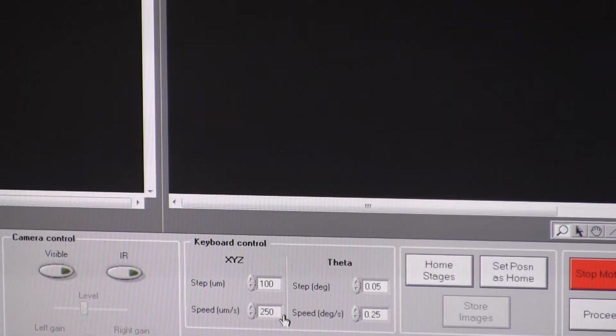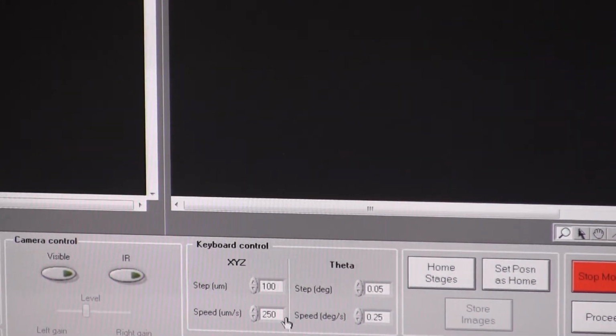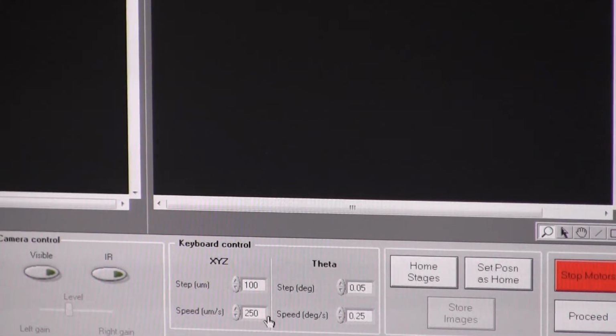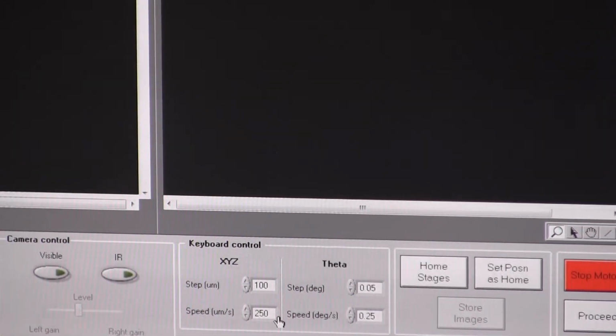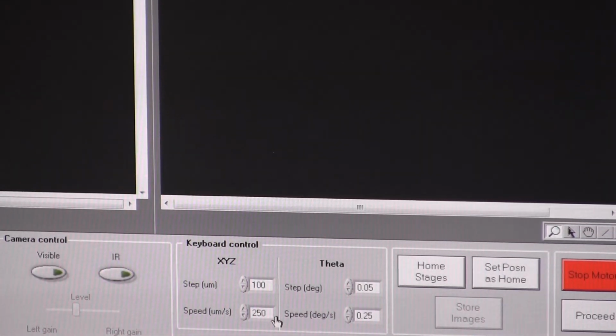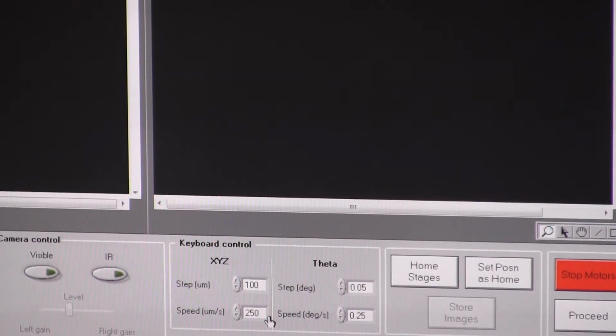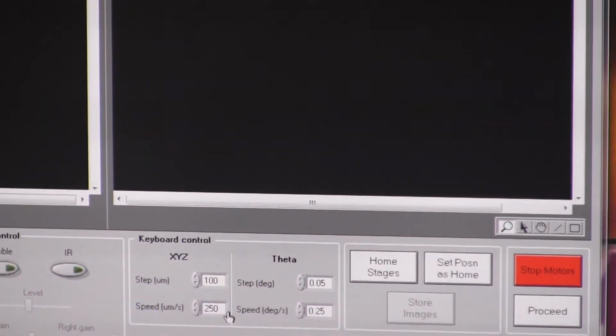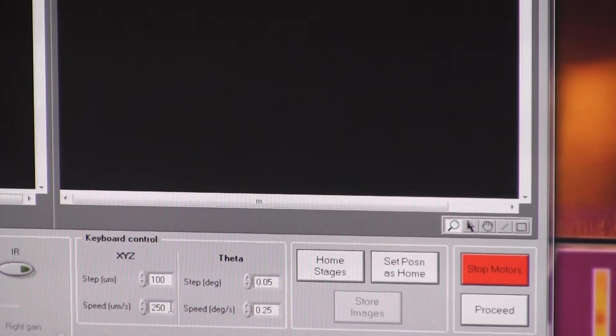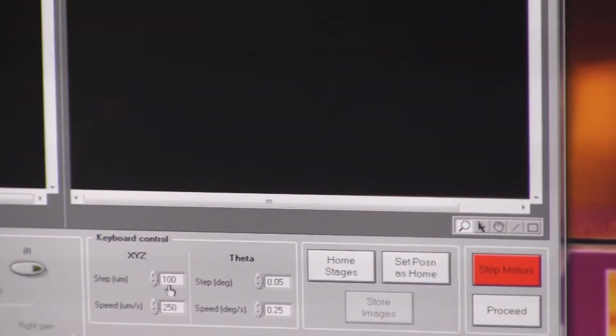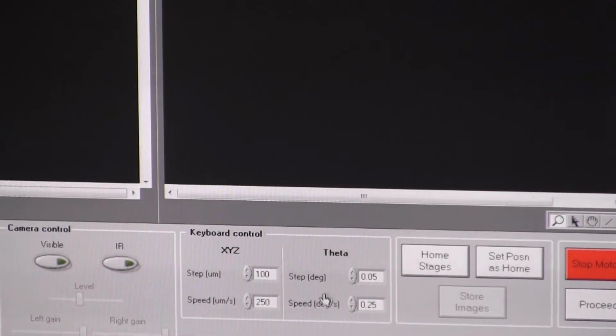So that's if the alignment marks are not in the field of view when you start and you need to do a spiral search, you'd be holding the button down rather than doing it in 100 micron steps all the time. So it will use that parameter to control the speed, and it will use this parameter to control step sizes if you do 1 push at a time.